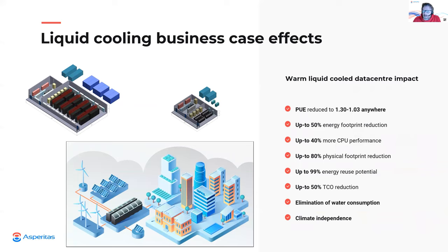So the liquid cooling strategies also have a tremendous impact on TCO models. These effects are caused by the consolidation of IT, which is made possible by the higher achievable densities with liquid cooling and the ability to work with elevated temperatures. Some of the effects may conflict with each other, so this list should not be considered as a cumulative list. The TCO effects apply to any liquid cooling strategy and depend on how far liquid cooling is optimized across a facility.